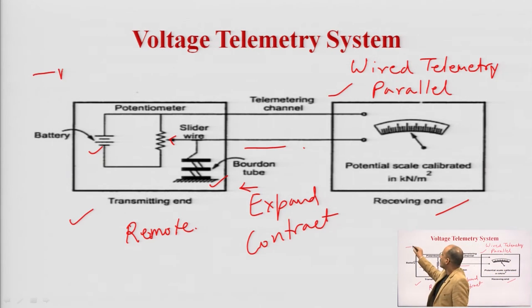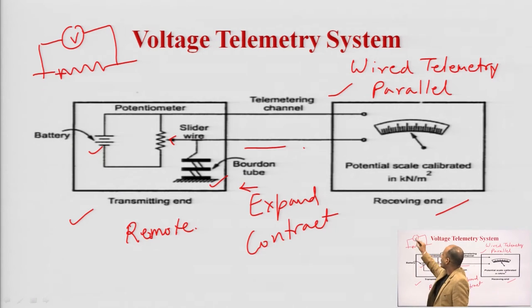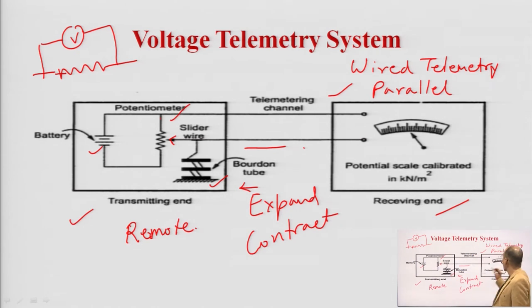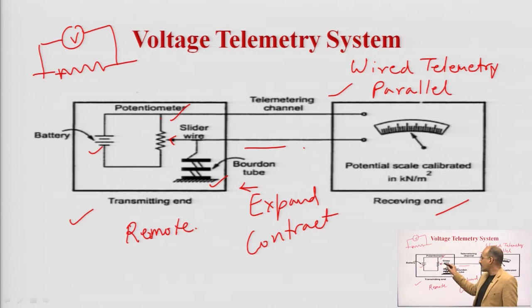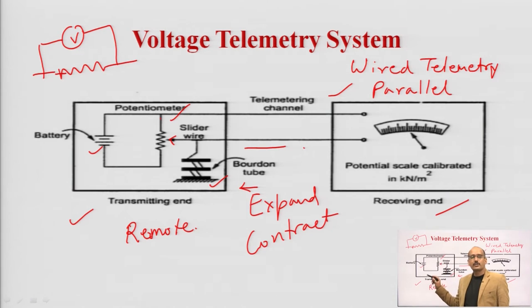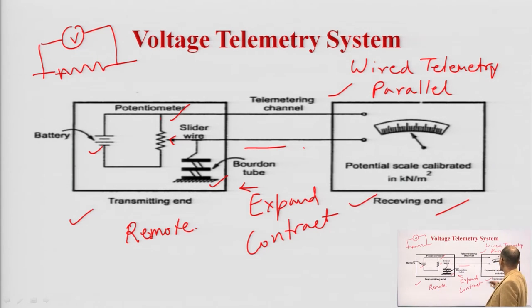Whenever you want to measure the voltage across any system, you always connect the voltmeter in parallel. Here you can see that the potentiometer is connected in series, but the voltmeter — or the potential scale calibrated for voltage measurement — is connected in parallel. As the Bourdon tube expands or contracts with pressure, the position of the slider wire changes. That changes the resistance of the potentiometer, and that change in potentiometer resistance is measured in the form of voltage at the potential scale through connecting wires, also called telemetry channels.